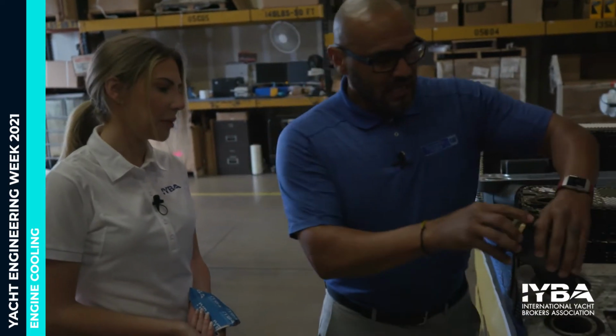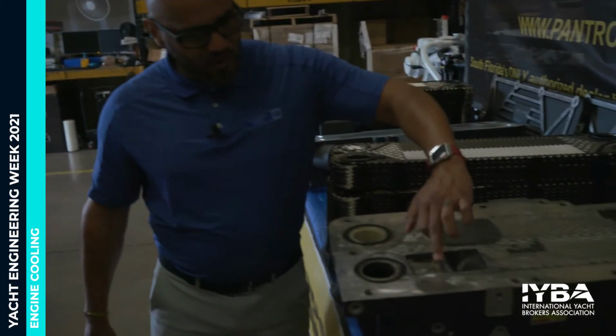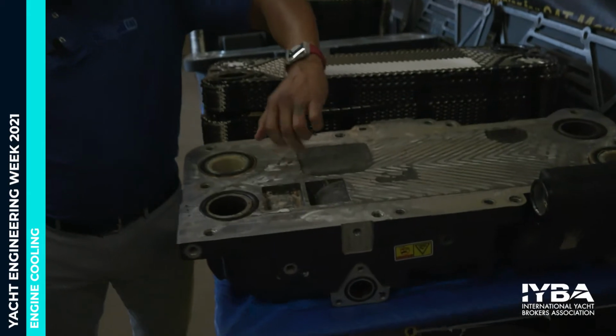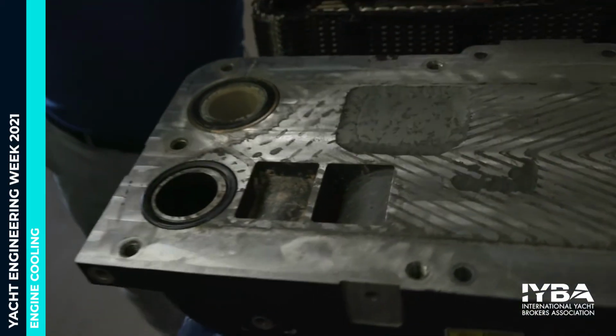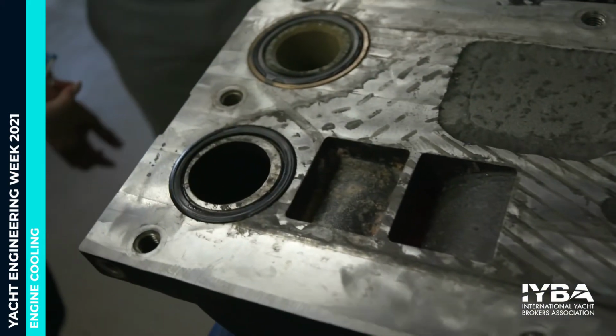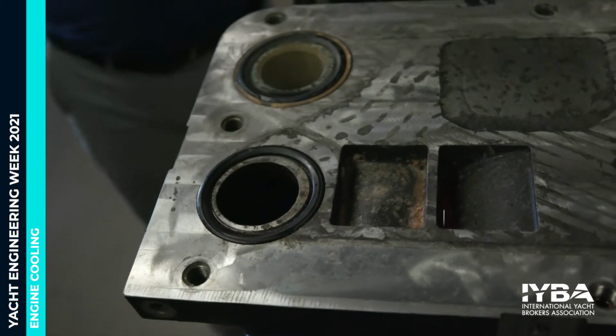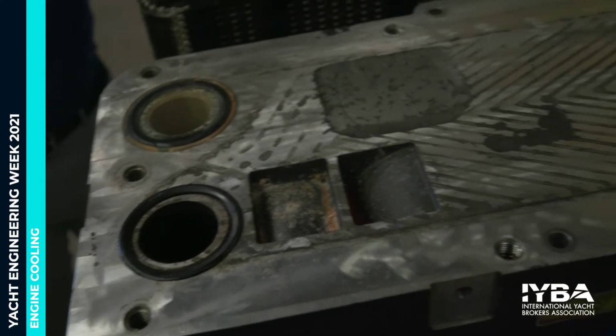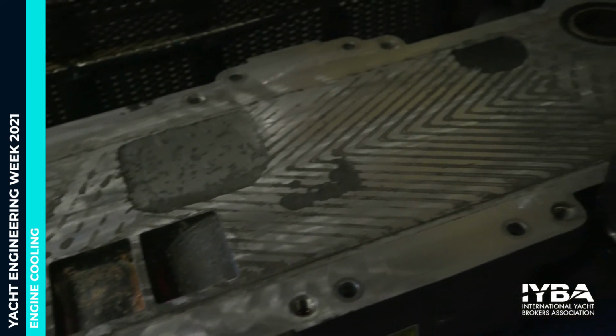You can start to see some of the corrosion that comes in here, some calcium buildup around the rings. All this gets cleaned in the process. When we take these apart, it all gets cleaned and polished again, making sure the surfaces are flat so they'll be able to seal properly.